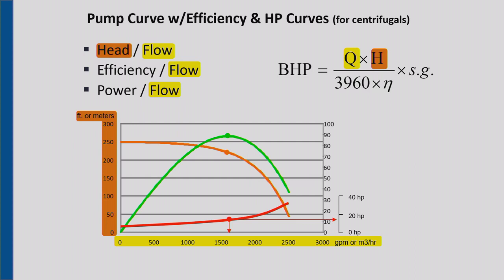That's the vertical axis. So I've got flow and I've got head, okay? I've got flow and I've got head in the equation. I've got flow and I've got head on the pump curve on the chart. And that describes all the possible heads and flows that pump can do. I can have a lot of flow out here, 2,500 gallons per minute and only 50 feet of head, or I could deadhead it and shut it off, close it down completely, and I'd get 250 feet of head. Anywhere in between the two is where that pump can operate.